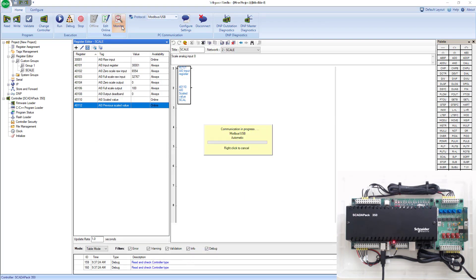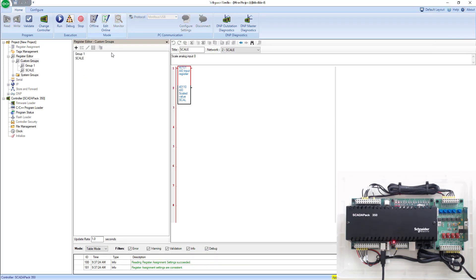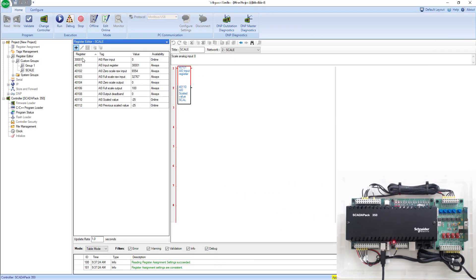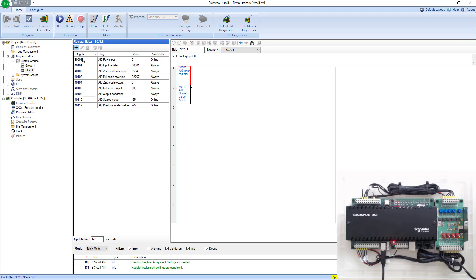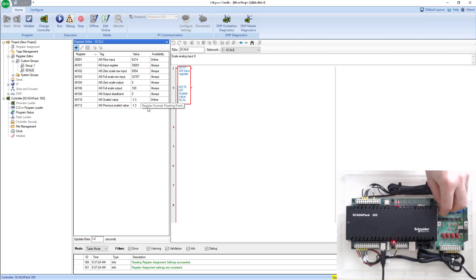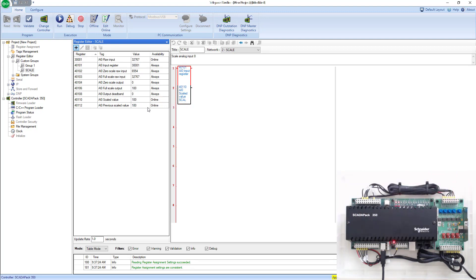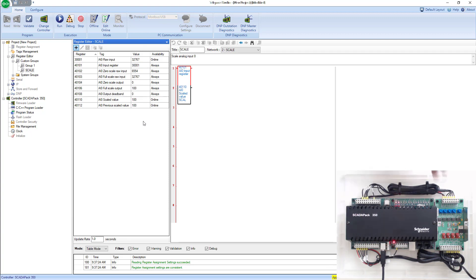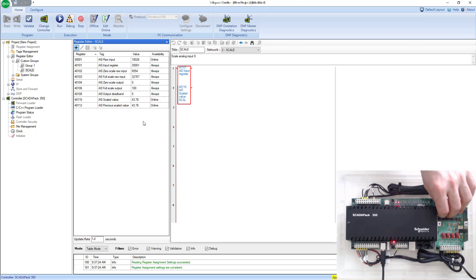Now that you're all set up, you can hit monitor, go back into our scale group. Now that we're in our scale group, we can turn up that pot. Go up to 32767. We see here that AI0 raw input is 32767, and we know that the AI scale value is 100. We're getting the same values, just a lot easier to diagnose now that we can see the tag names of each register.